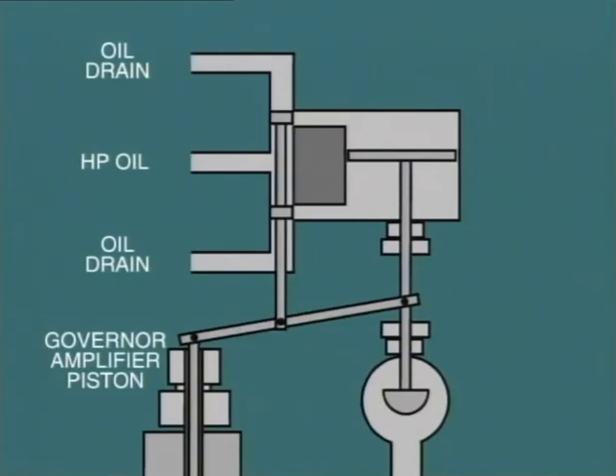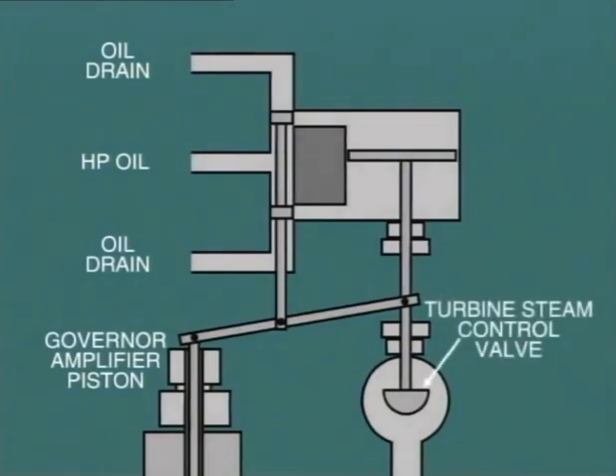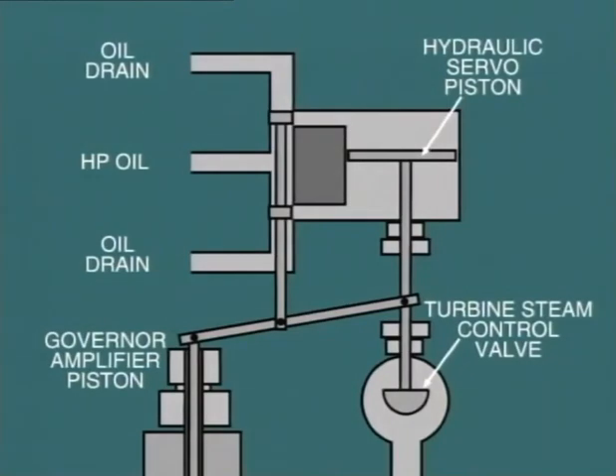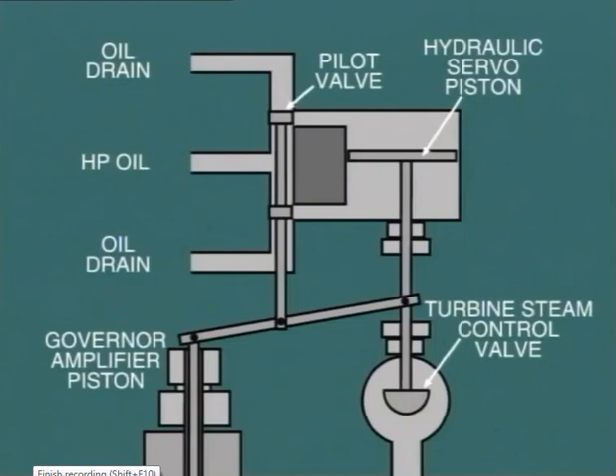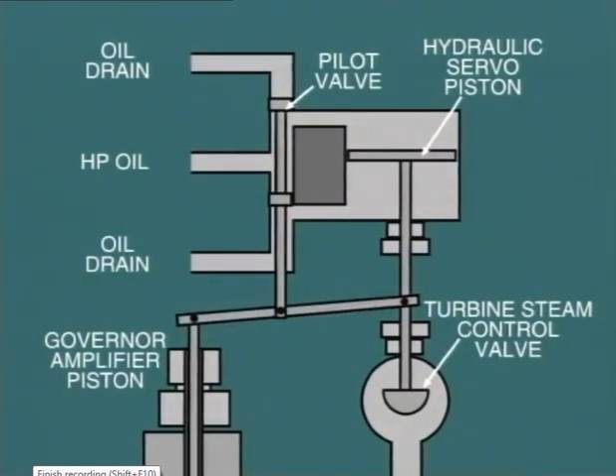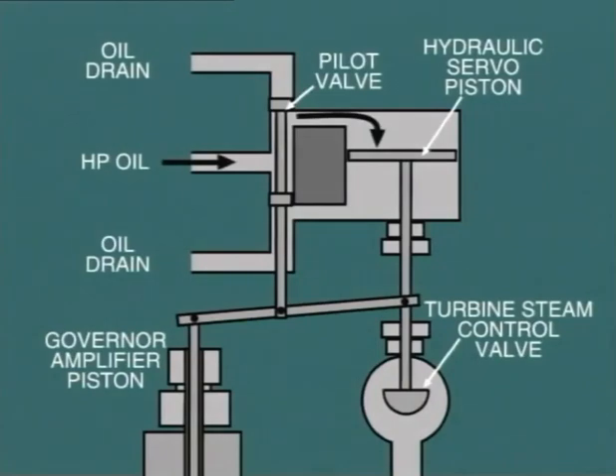In this simplified example shown here, the turbine steam control valve is adjusted by the position of the hydraulic servo piston. This large system is controlled by the small pilot valve here. Suppose the governor control system lifts the operating lever slightly. As we can see, this will now allow high-pressure oil to enter the servo cylinder above the piston.